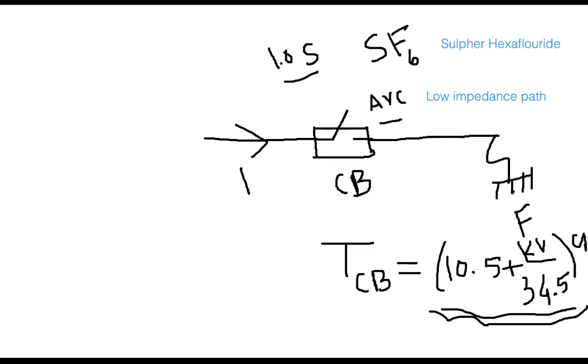So that's why you get that minimum value. Now you will be comparing. First fault happened, you constructed this waveform of total kinetic energy. You look for where the minimum point is, there may be several. You first look at the first minimum and make sure that this time is greater than this time. If that time is greater, meaning the arc has been extinguished, now it is safe to reclose the breaker. If not, you go to the second point.